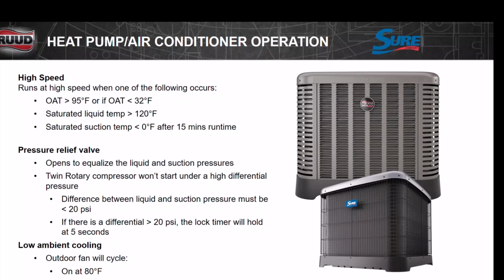We have our pressure relief valve in the unit. It utilizes suction pressures. Rotary compressor, so it equalizes the compressor like we talked about earlier, so the compressor will start. We want to start with less than 20 psi across that compressor. If it's more than 20 psi across it, the lockout timer will hold it for 5 seconds before it starts and give it time to relieve that pressure.